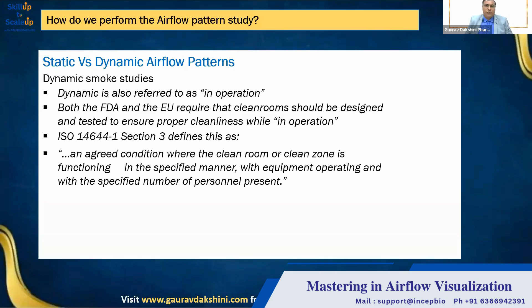Typically, US FDA requires only the in-operation (dynamic) study to be done; FDA doesn't ask to see the static study. But the EU is different—it recommends doing both static and dynamic. So if you're a facility focused only on FDA regulation and not dealing with other regions, you should only do the in-operation study. But for facilities under EU guidelines, it's recommended to do both static and dynamic studies.